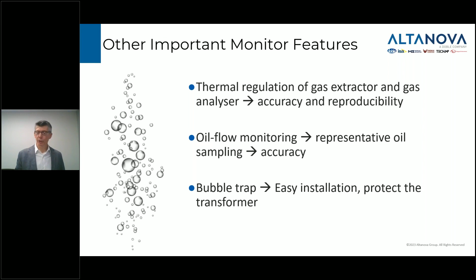Oil flow monitoring is very useful. We've had cases over the years where people accidentally valve off a monitor and don't realize it for years to come, so it's nice if the monitor can check that oil is truly flowing and otherwise report an error condition. Finally, a bubble trap is a useful feature to make sure that during installation and operation, gas bubbles arising in the monitor and oil lines can't make it into the main tank oil, where they could compromise the dielectric of the transformer.